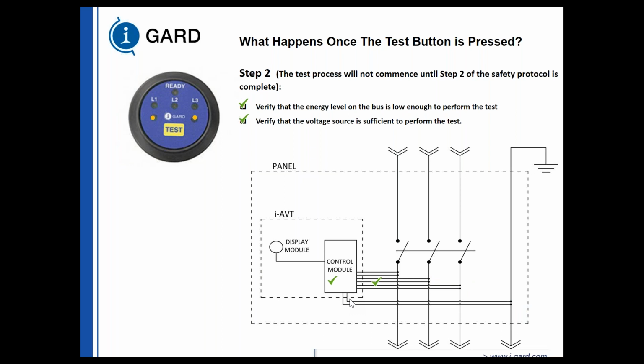Step 2. Verify that the energy level on the bus is low enough to perform the test, and verify that the voltage source is sufficient to perform the test. This is testing the capacitor to ensure that we have enough energy to perform another test.